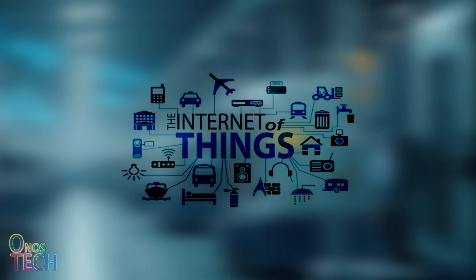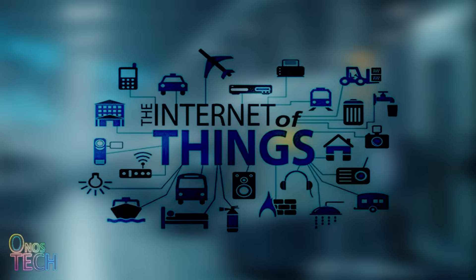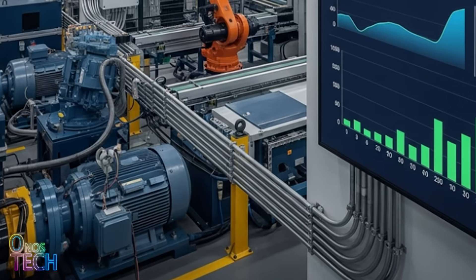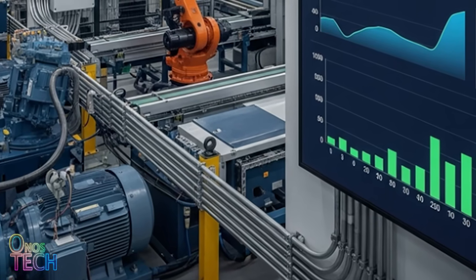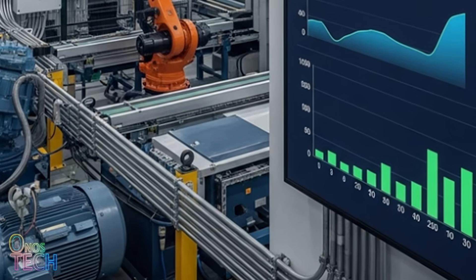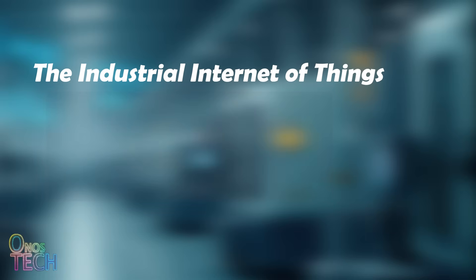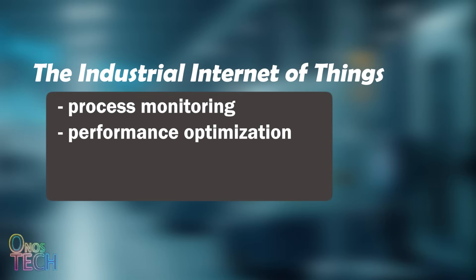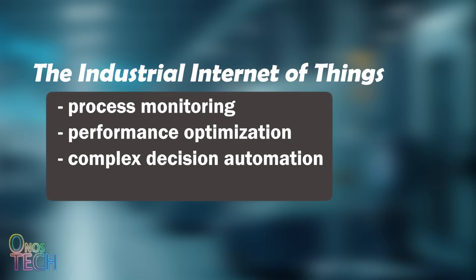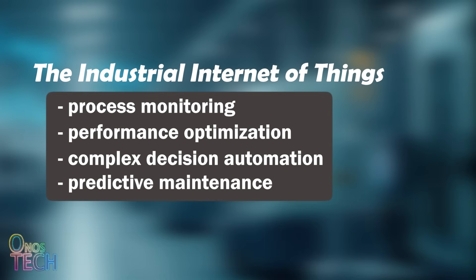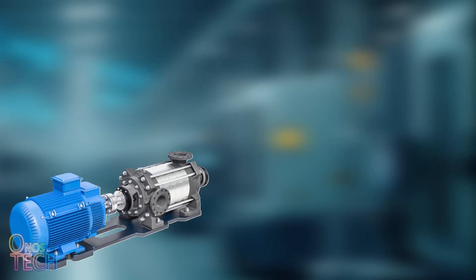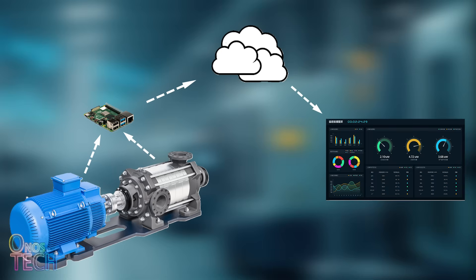The IIoT takes IoT technology — sensors, data, and the cloud — and applies it to industrial environments where there are machines, transmitters, actuators, controllers, and the SCADA system at large. IIoT intelligently monitors processes, optimizes performance, automates complex decisions, predicts failures before they happen, and automatically triggers maintenance. For example, vibration and temperature sensors on a pump stream data through a gateway for analysis and trigger maintenance automatically. This is one of the most common IIoT applications: predictive maintenance.